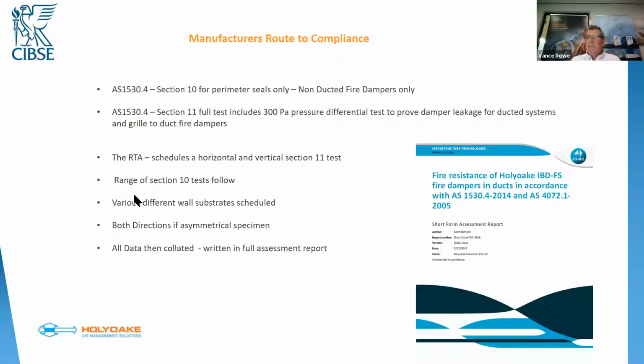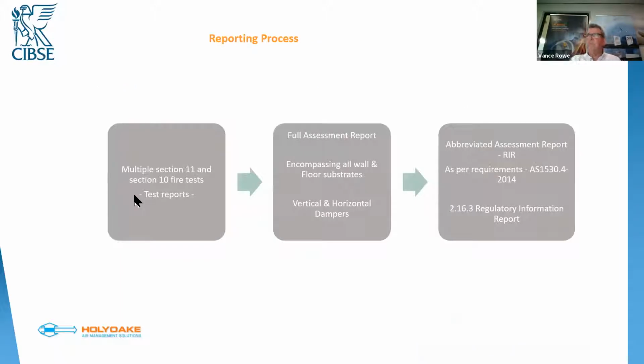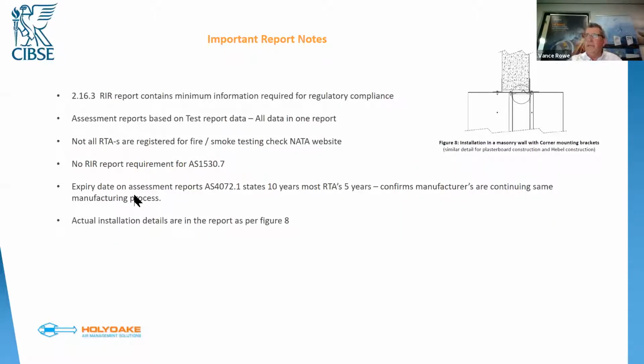If the test specimen is asymmetrical, it needs to be tested from both directions, or it needs to have an arrow so that people understand the direction of airflow within the report itself. Again, I've got a slide just encompassing that, and hopefully that makes it a little bit easier to see. I've got in there 2.16.3, which is the information on the regulatory information report.